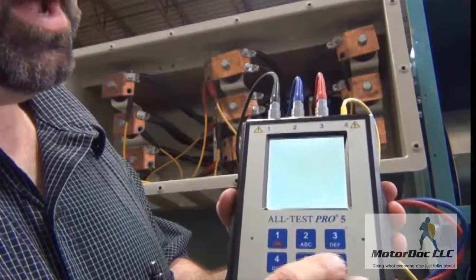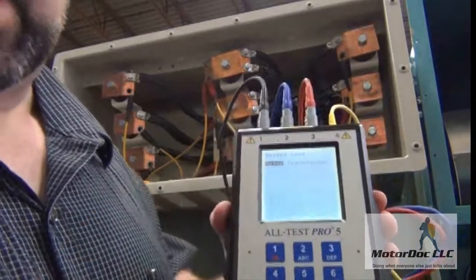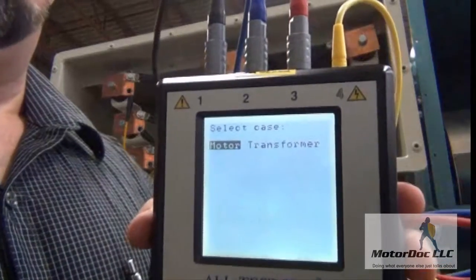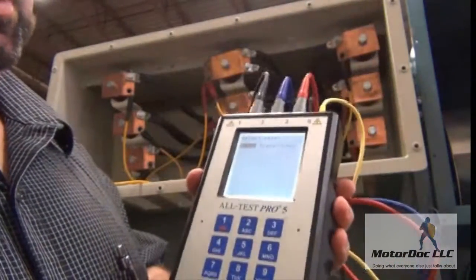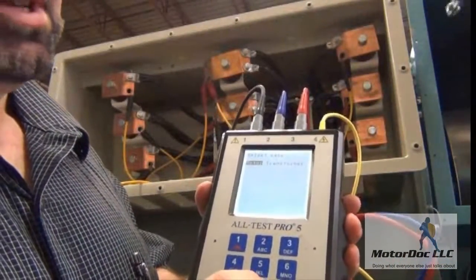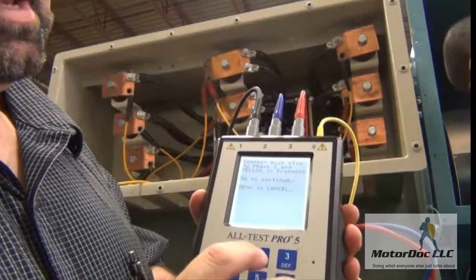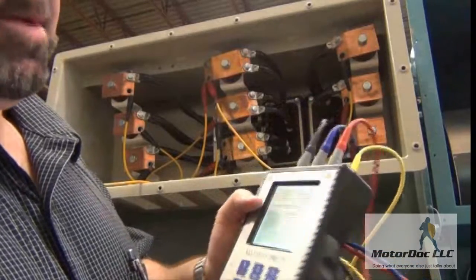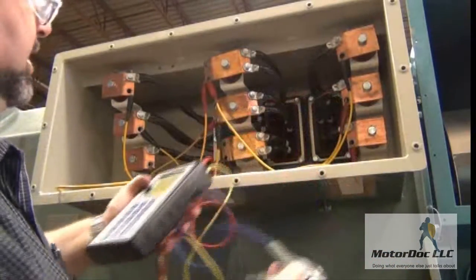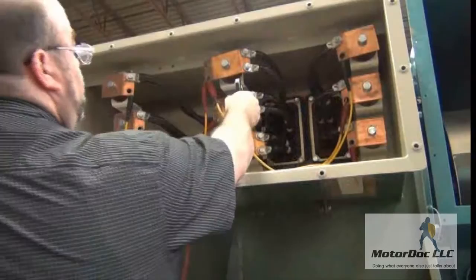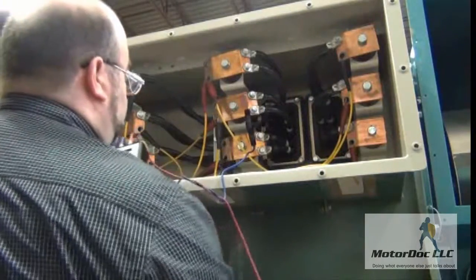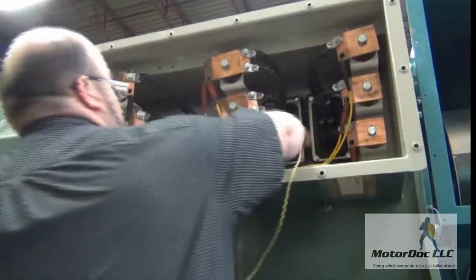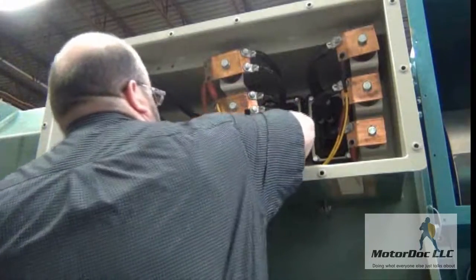This is the All-Test 4 tests plus the All-Test 33 tests. If I click OK, it says motor or transformer. This machine is designed to test motors and transformers as well as DC machines of all types. We're going to select motor. It says connect the blue clip to phase 2 and the yellow to any frame ground. I'm going to take the blue clip, connect to phase 2, and connect to a ground inside the machine.